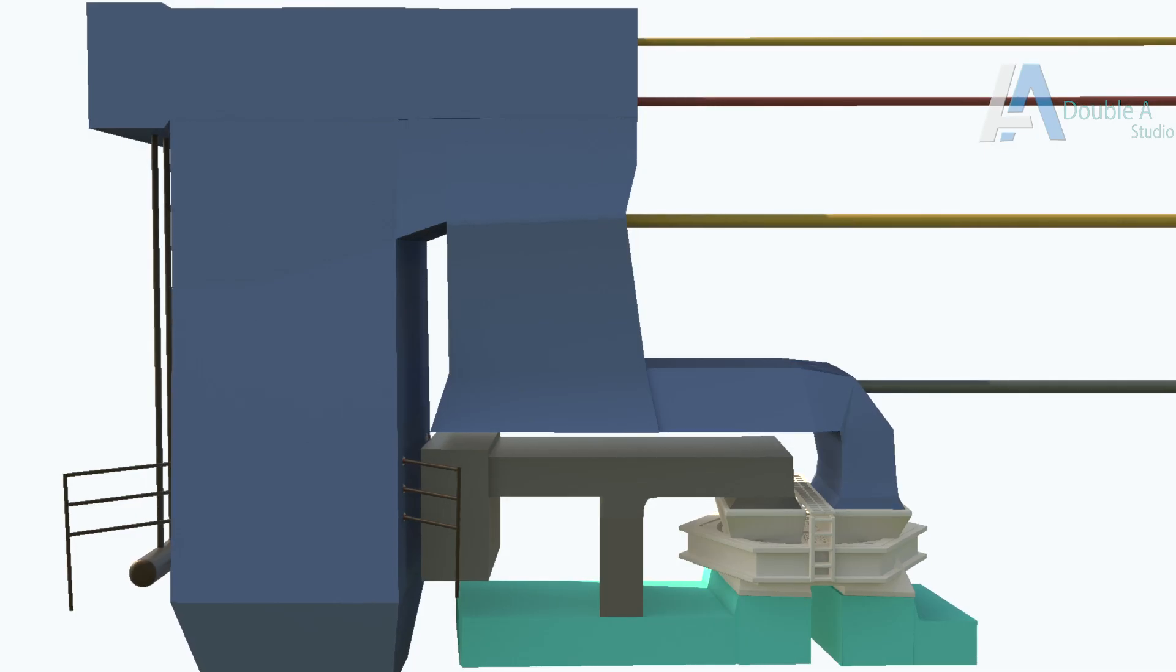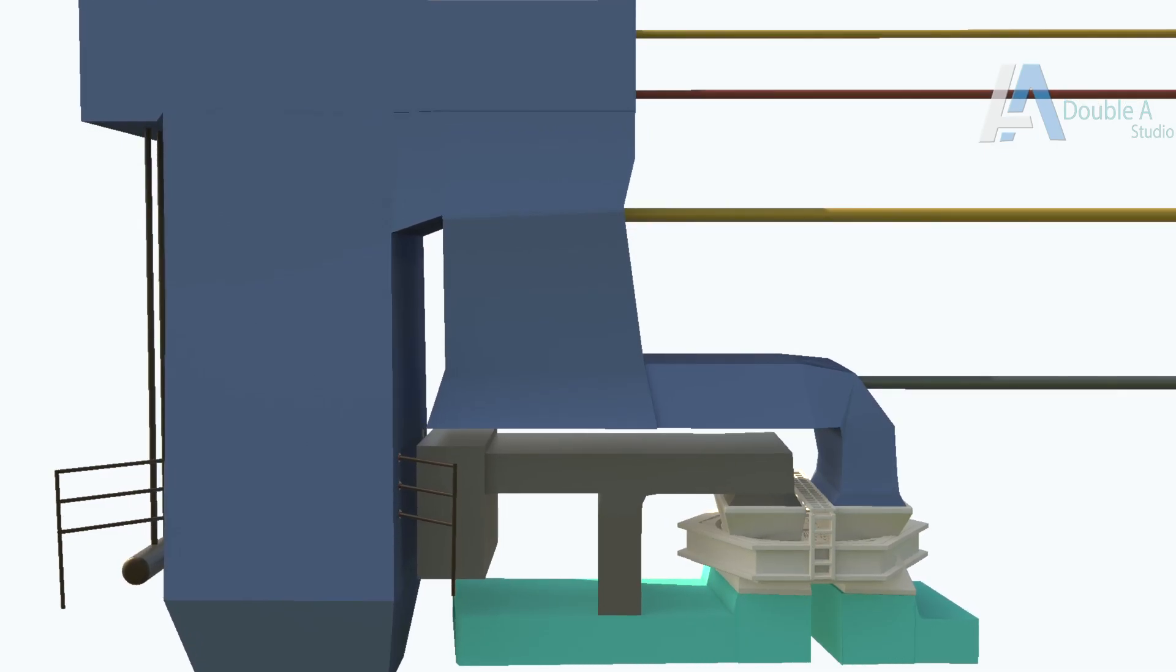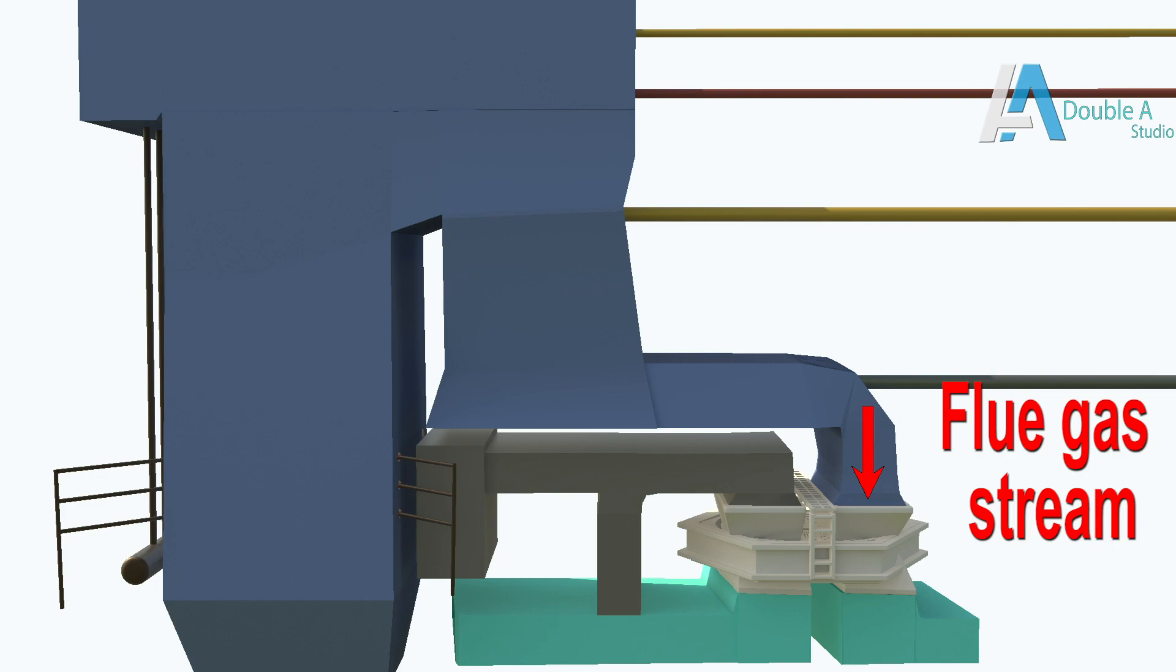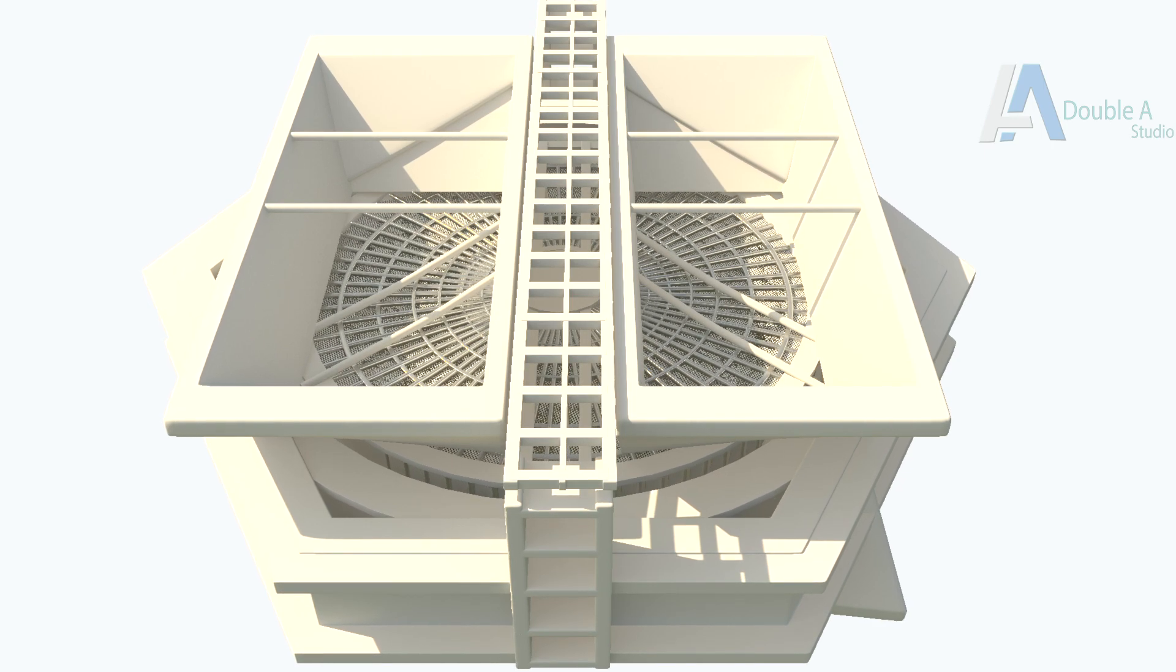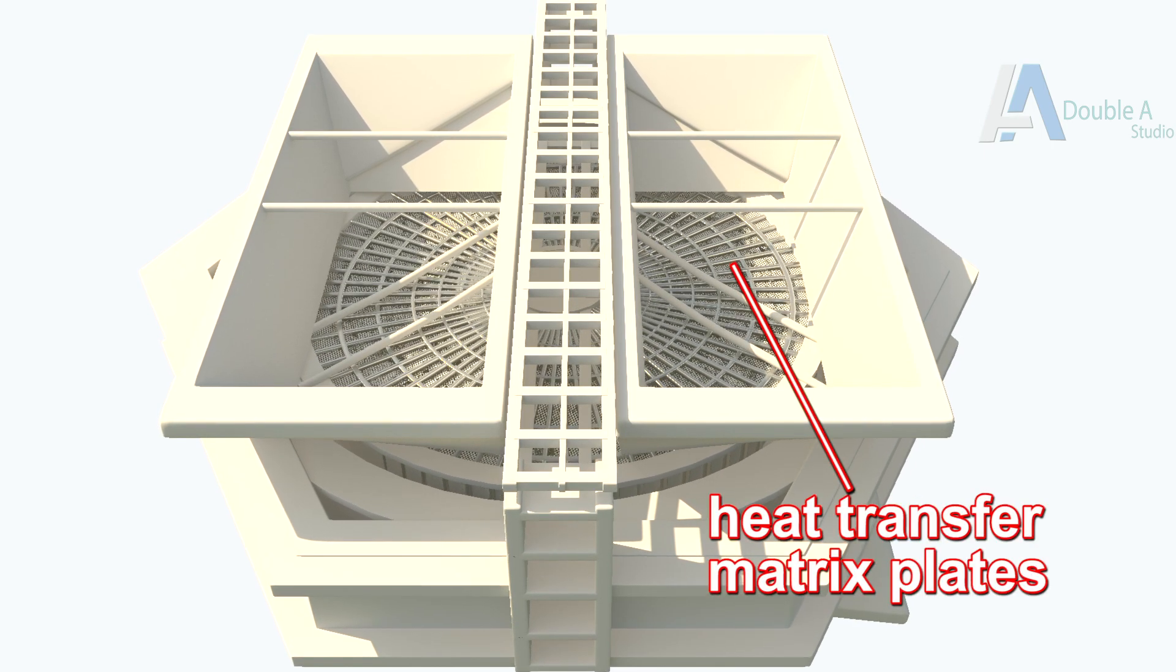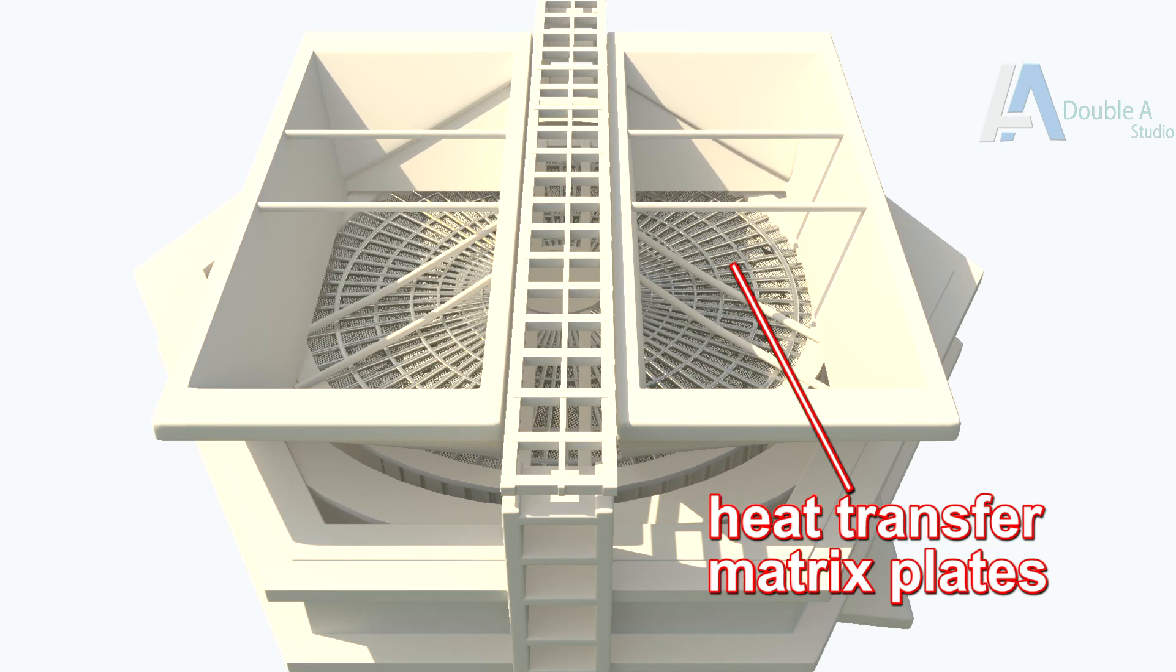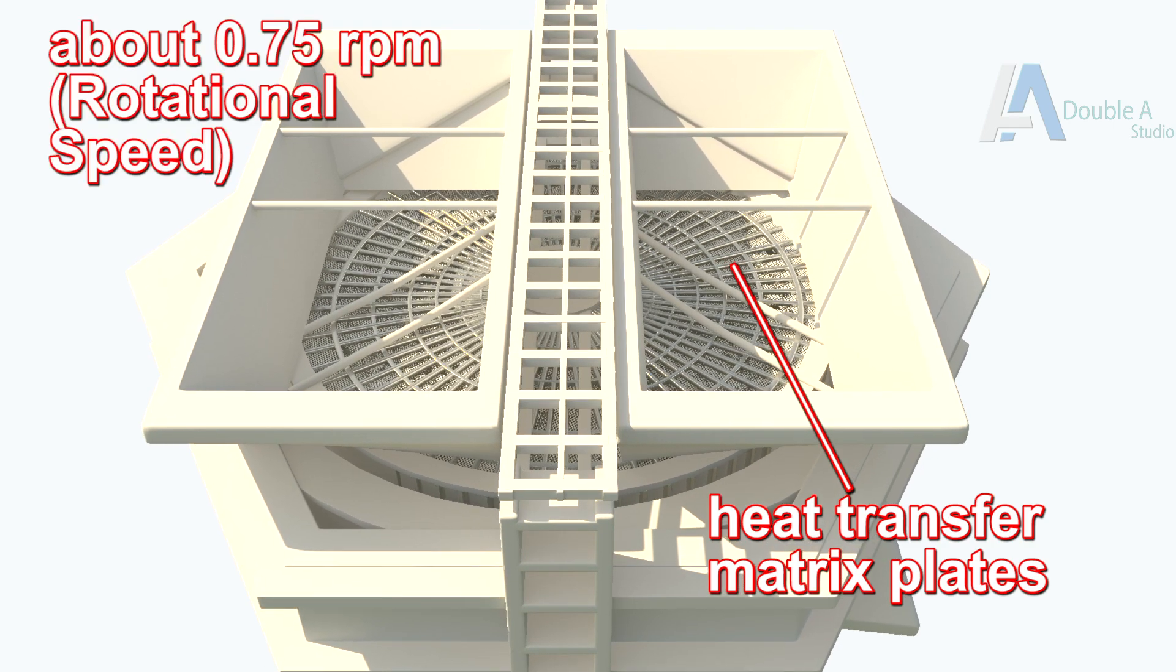The term tri-sector stands for single flue gas and two out streams of air called primary and secondary air. At inlet duct, forced draft fan forces ambient air which on heating diverts as primary and secondary air. It has rotating part which is closely packed with heat transfer matrix plates. The rotor rotates at very slow speeds, about 0.75 RPM.